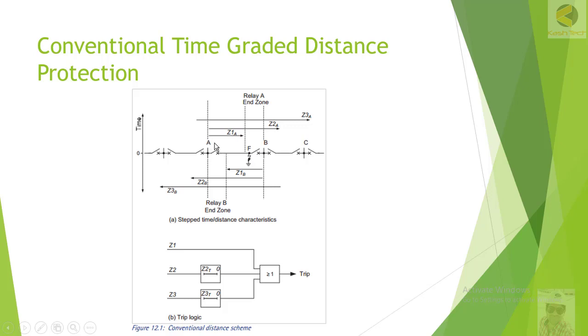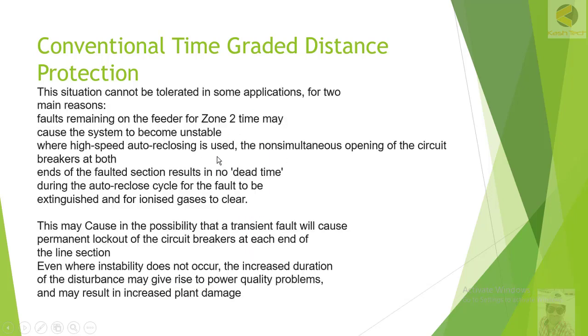If one breaker opens immediately and the second opens with a time delay, the dead time is increased. For example, if the arc is completely extinguished at 100 milliseconds after the first breaker opens, but the Zone 2 time delay is 400 milliseconds, we are keeping the arc fed for 300 to 400 milliseconds unnecessarily. This delays auto-reclosing and delays restoration of system stability. This is another reason we do not want to accept this condition.